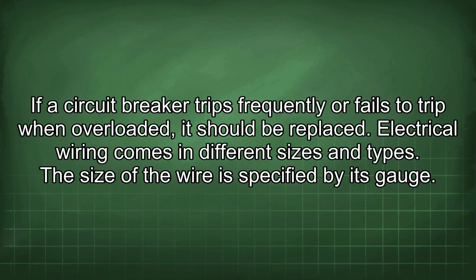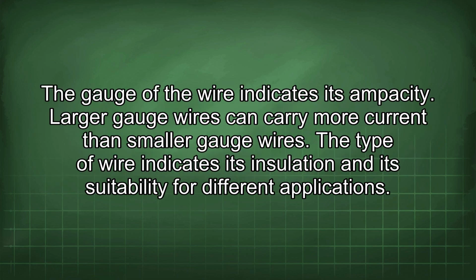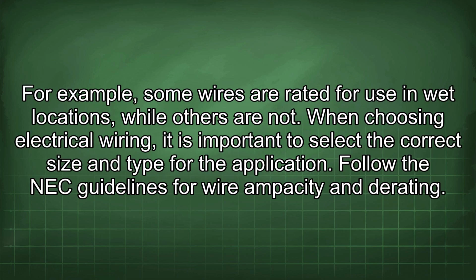Electrical wiring comes in different sizes and types. The size of the wire is specified by its gauge. The gauge of the wire indicates its ampacity. Larger gauge wires can carry more current than smaller gauge wires. The type of wire indicates its insulation and its suitability for different applications. For example, some wires are rated for use in wet locations, while others are not. When choosing electrical wiring, it is important to select the correct size and type for the application.